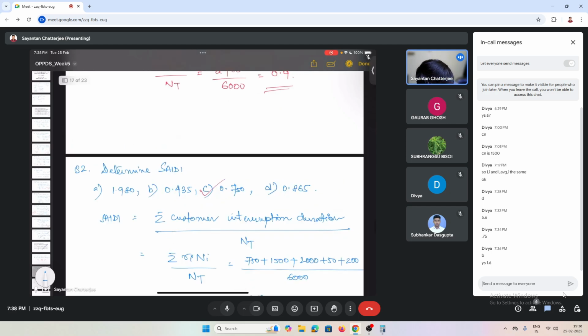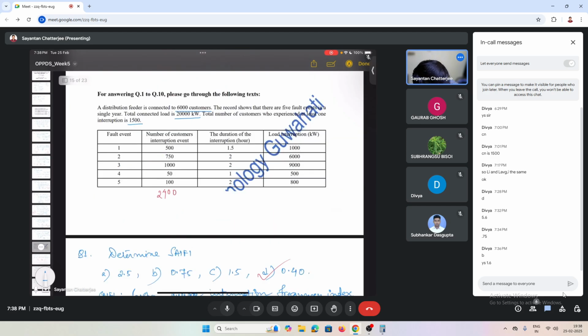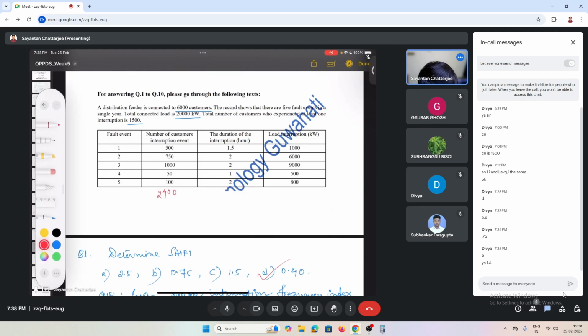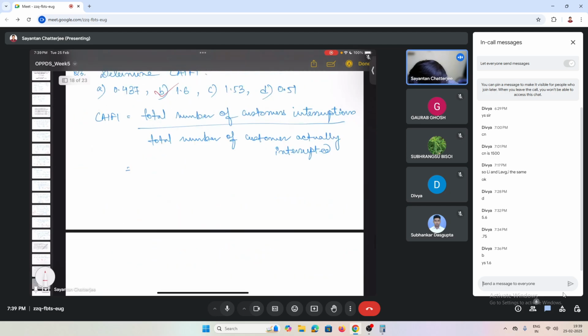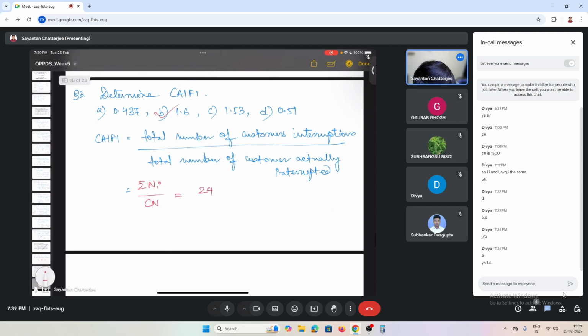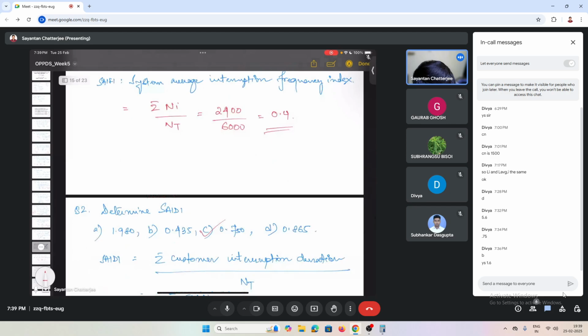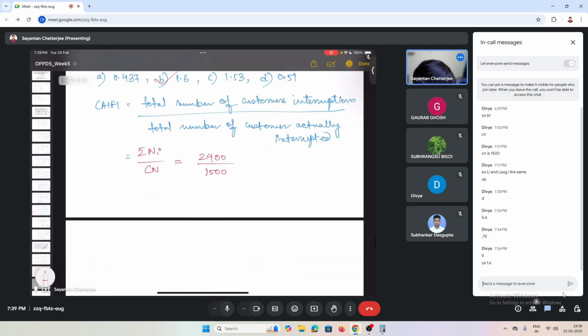The total number of customer interruptions is NI, and this one is the total number of customers actually interrupted, CN. So it is the summation of NI by CN. NI was 2400 and CN is 1500. So the final answer is 1.6, right? Yes.